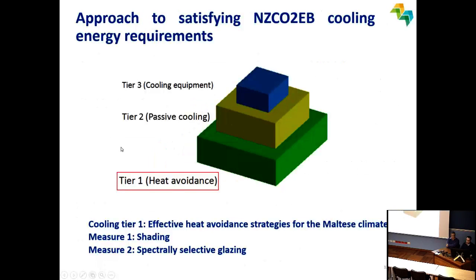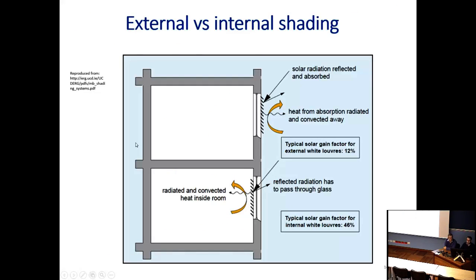Let's start with the first factor, heat avoidance. The most important technologies for Malta are shading and spectrally selective glazing. There are two types of shading, external and internal. External shading is much more effective than internal shading, but it is more expensive. The typical solar gain factor for external shading is 12%, while for internal shading it is inferior, at 46%.